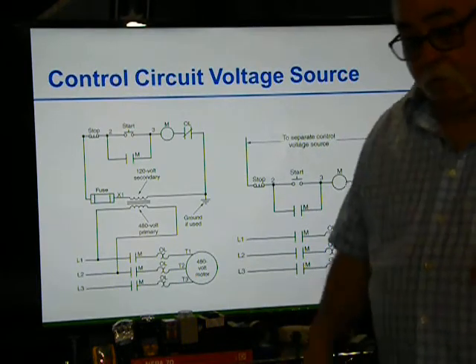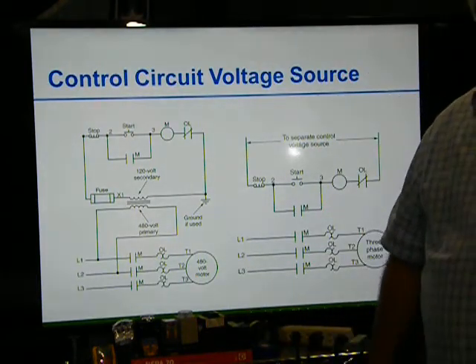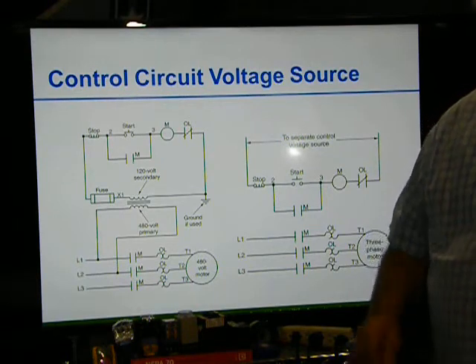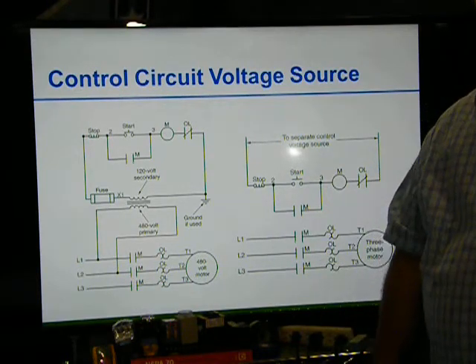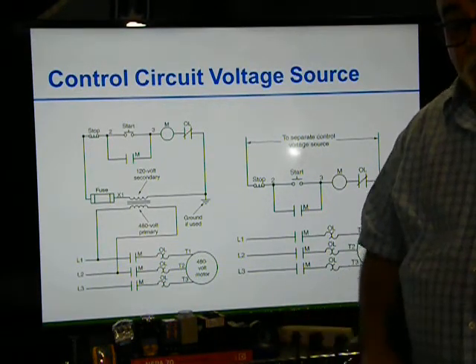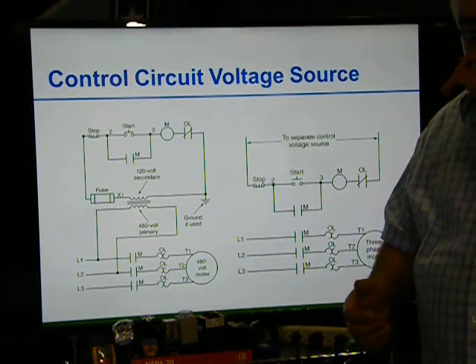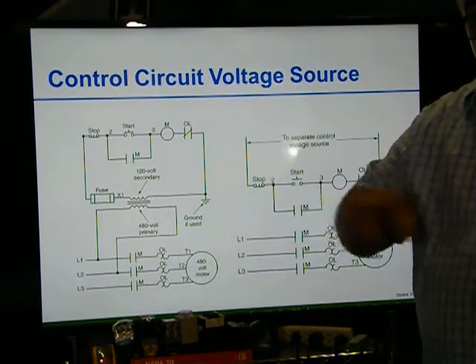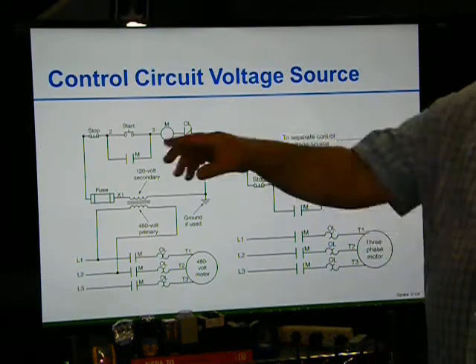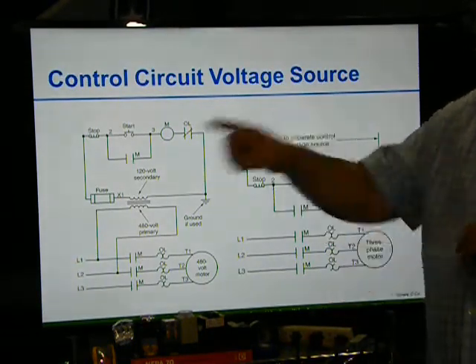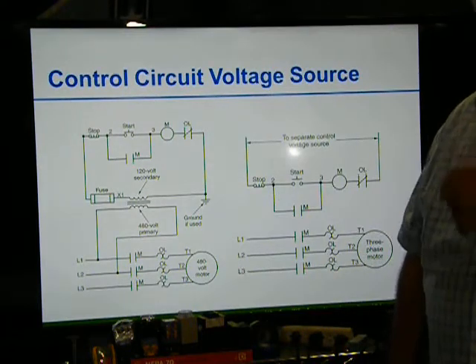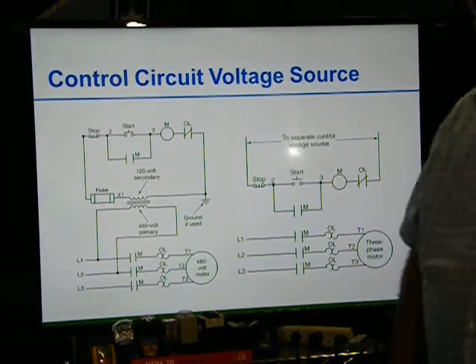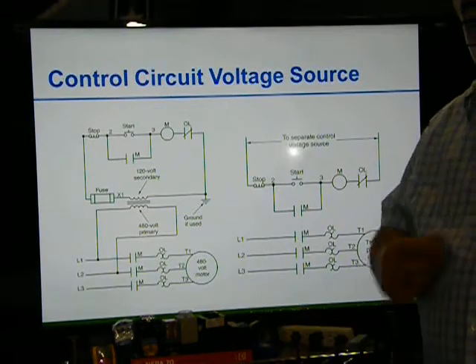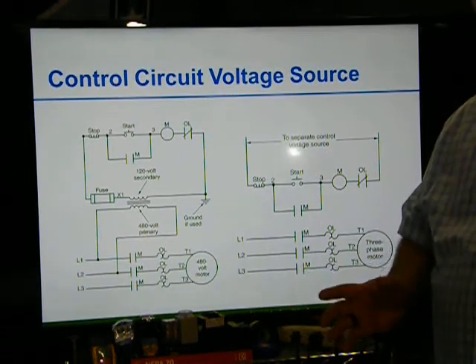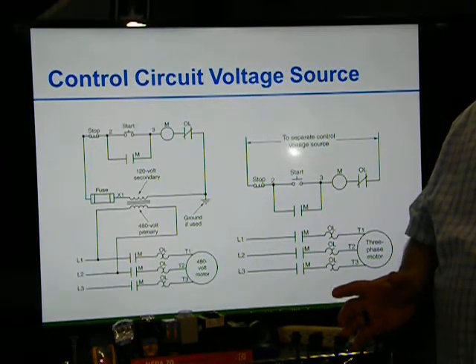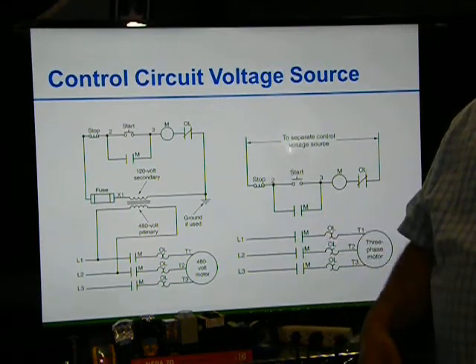I've had it many times when we get motors. We're changing out a motor, and a lot of times, the motor's burnt, so we can't check it. But a lot of times the engineers that have worked in the area would mark the direction of the motor turn, or the direction of whatever the fan is turning. Okay, it needs to go clockwise or counterclockwise, so they would have it labeled. So all of a sudden we go in there, the motor burned out, we change the motor out, we hook it up exactly the same, and all of a sudden the motor's going in the opposite direction.